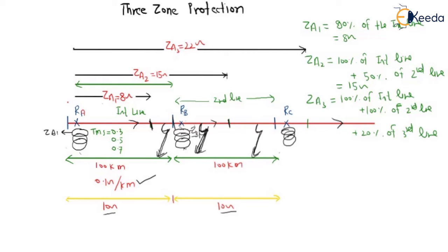You can watch in other terms: if the fault occurs here and disc number 3 moves, and let us assume B has failed, how will we ensure that the fault occurred here? If the third disc moves, it means the fault occurred in the 150% to 200% line.